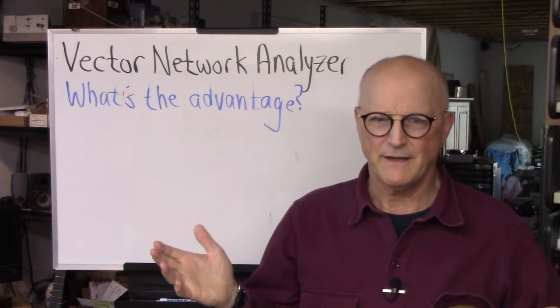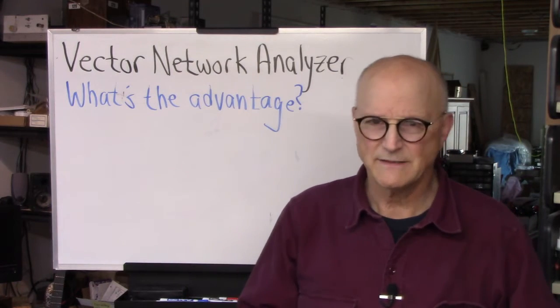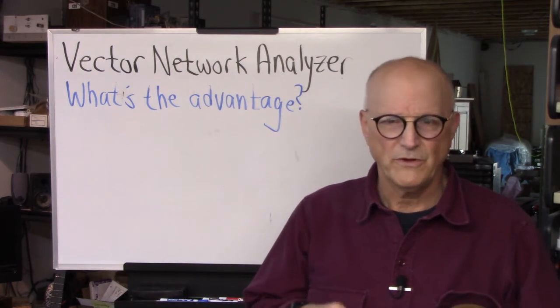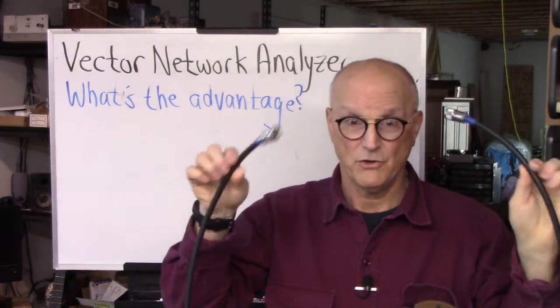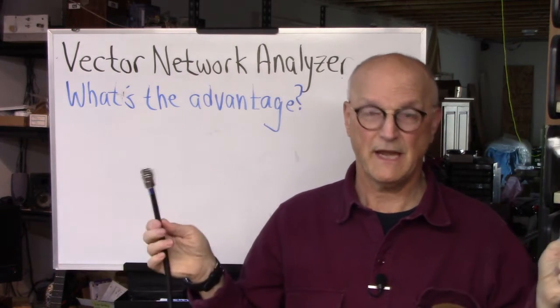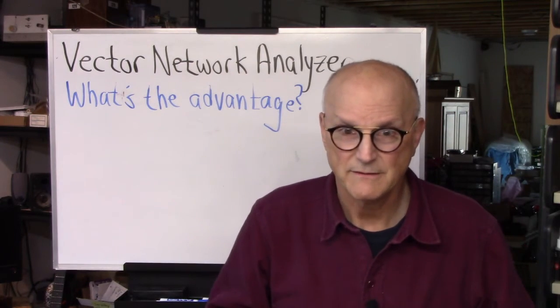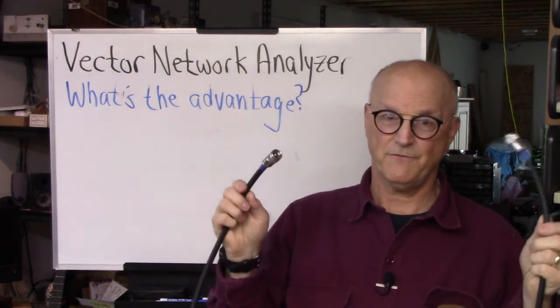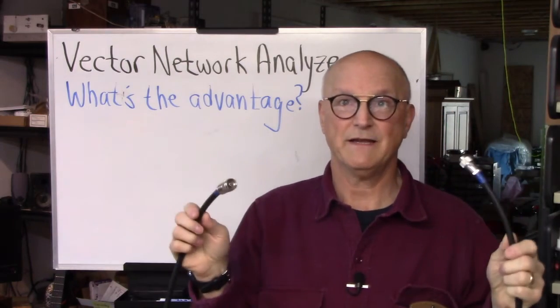Well everything has some kind of electronic signature. When you make a measurement using a cable to connect your test instrument to the unit under your test, the cable can affect that measurement, especially if you're measuring something involving impedance.